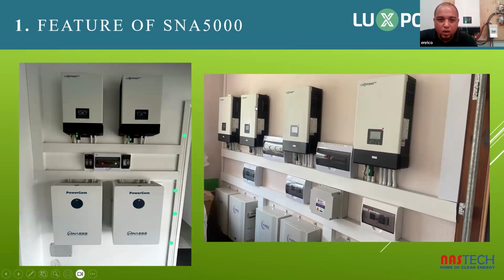Here's another example of paralleling the 5 kilowatt inverter. You can do a 3-phase paralleling. So the first inverter is the master inverter. The second is the sub inverter, third, second sub, and the fourth is the third sub. Different installations are done differently. These are your PV photovoltaic protection boxes, and these are your battery protection boxes. These are just two examples of the manner in which you can do the installations with our SNA 5 kilowatts.